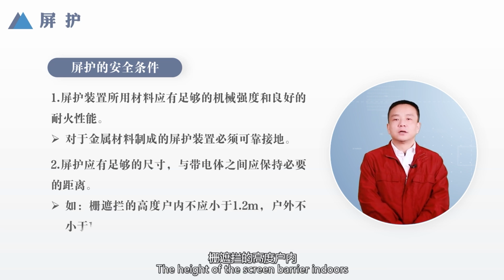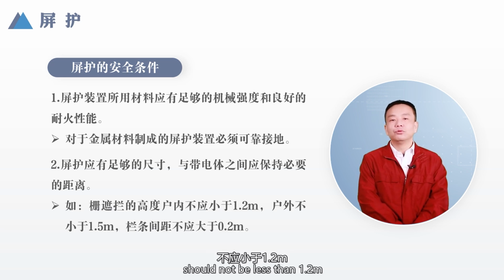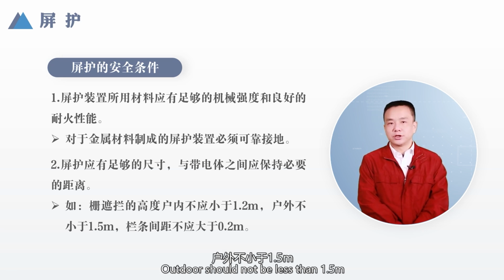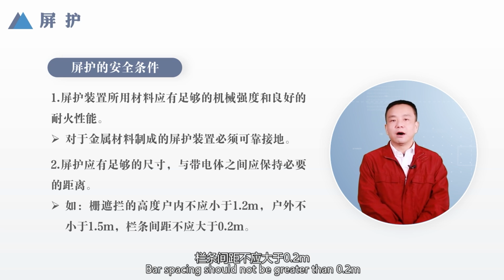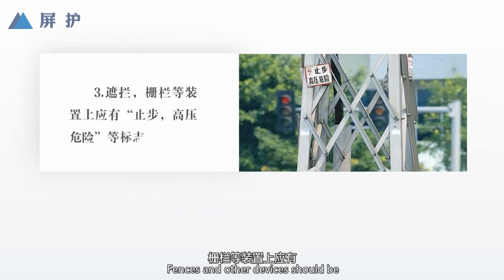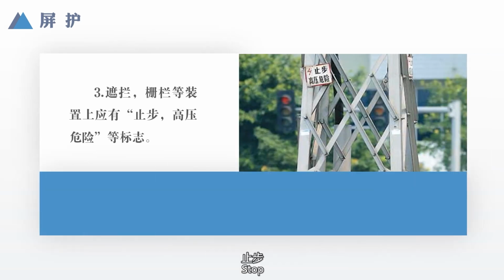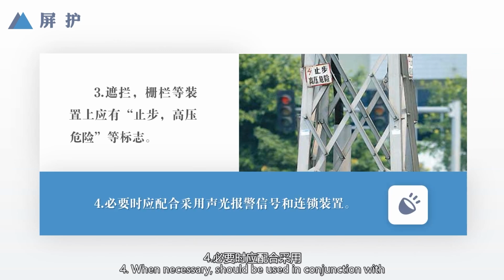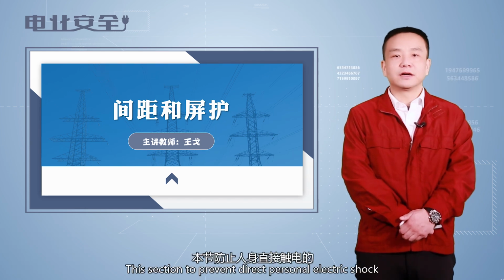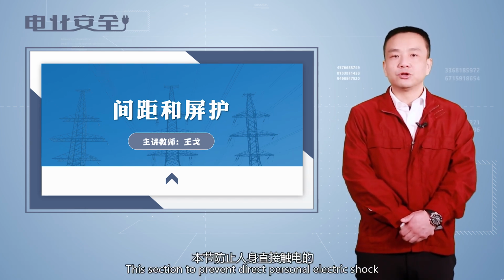For example, the height of the screen barrier indoors should not be less than 1.2 meters. Outdoors should not be less than 1.5 meters. Bar spacing should not be greater than 0.2 meters. 3. Screening fences and other devices should be fitted with stop and high voltage danger signs, etc. 4. When necessary, should be used in conjunction with audible and visual alarm signals, and interlocking devices should be used where necessary. Okay, this section to prevent direct personal electric shock.